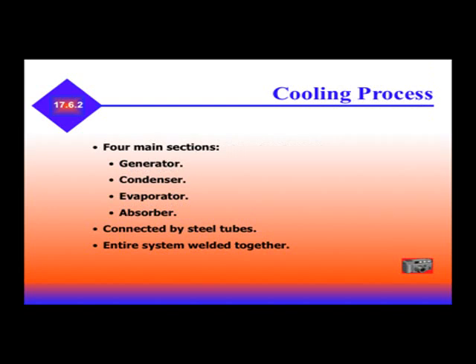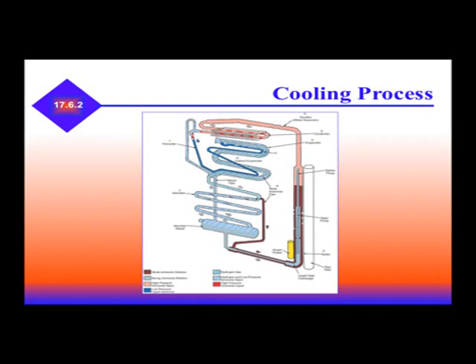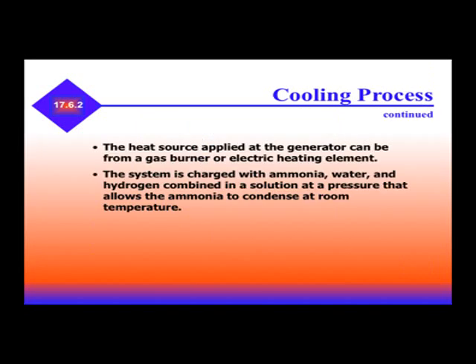Again, we have four main sections: generator, condenser, evaporator, and absorber. It's all connected by steel tubes, and the entire system is welded together. The heat source is applied at the generator and can be from a gas burner or electric heat element. The system is charged with ammonia, water, and hydrogen combined in a solution at pressure, which allows the ammonia to condense at room temperature.